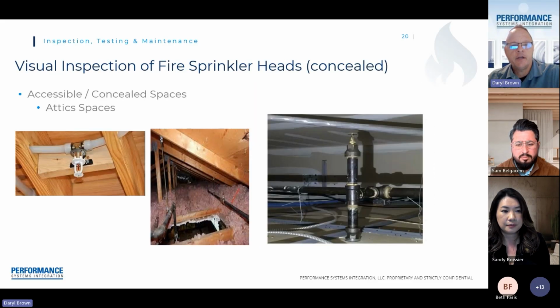In addition, every 5th year, we are also looking at fire sprinkler heads that are in accessible concealed spaces. As I mentioned before when I was showing you the fire sprinkler heads, as you look up, if it's a combustible space, as you can see there on the right-hand side above a drop tile ceiling, or the left-hand side above a residential room setting, there are sprinkler heads up there. We're required per code to look at those every 5th year. So if there's a hatch or any way accessible to take a look at those, we're required to do a visual inspection on those every 5 years.